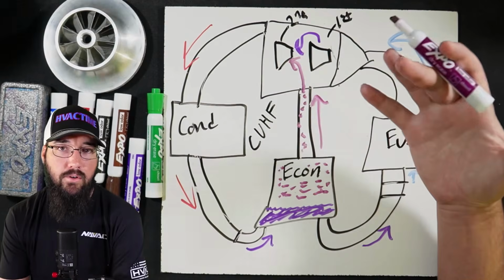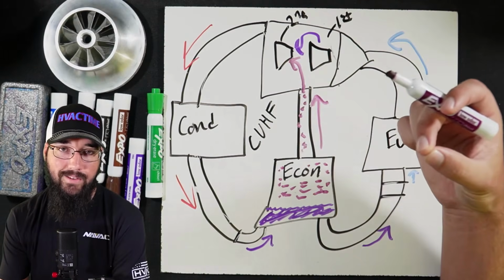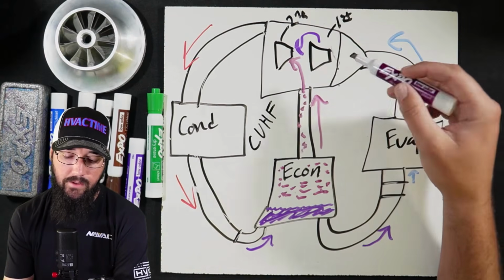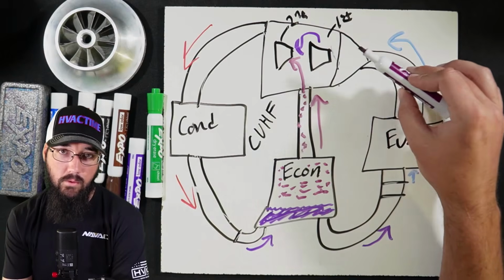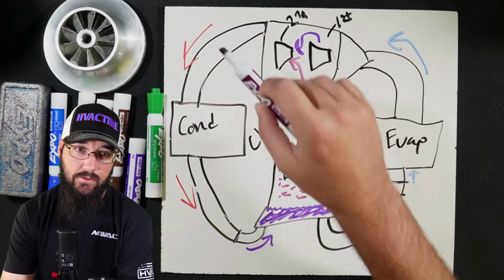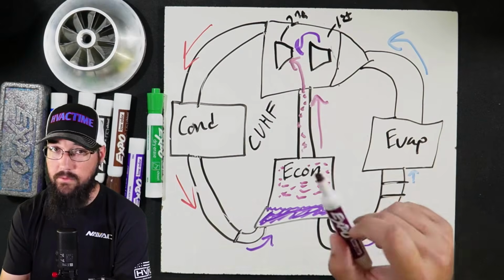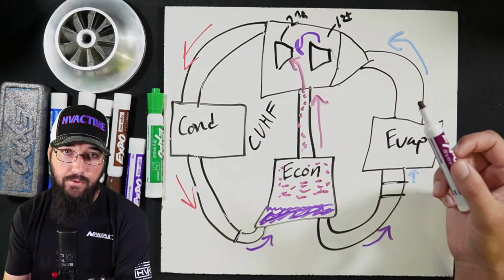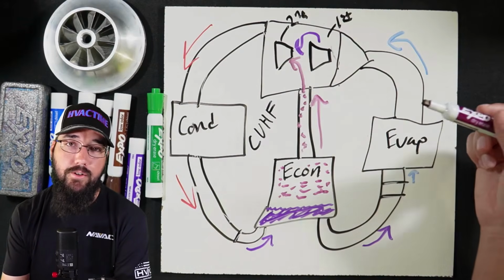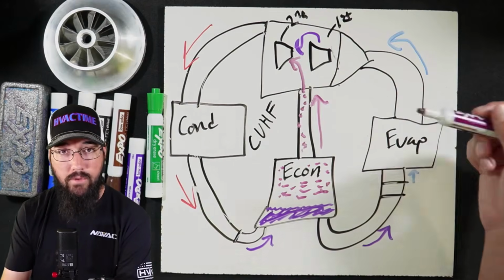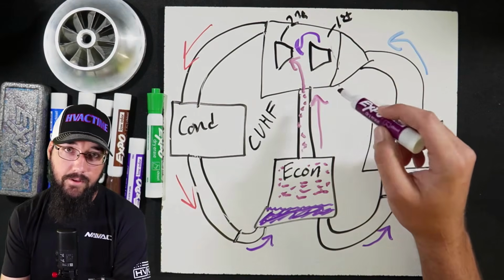Now, a big part of the work that our compressor has to do is compressing the refrigerant from its lower pressure state to its higher pressure state. This is true for any compressor, scroll compressors. The higher your compression ratio, the more energy you're having to use to make that compression. Same thing is true here.